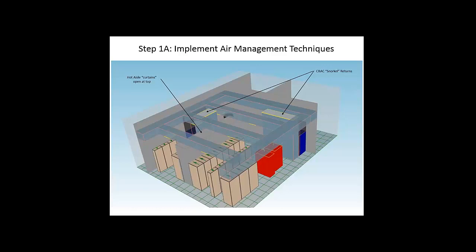One thing we could point out, Paul, is that if you compare those metrics with the original case, we have improved everything significantly just by pulling back on the airflow. Right. So there's a really big change here, much better already. Yes. But of course, you're going to show that you can fine-tune this now. You can go a little further.